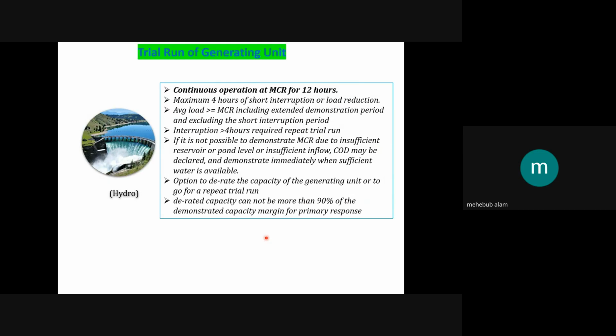Now for hydropower generators, we have to conduct the trial run for 12 hours. For thermal power plants it was 72 hours, but for hydropower generators the continuous operation required is 12 hours. Here also a maximum of 4 hours of short interruption or load reduction is possible, but interruption greater than 4 hours requires a repeated trial run. And here the derated capacity cannot be more than 90% of the total capacity of that generator.